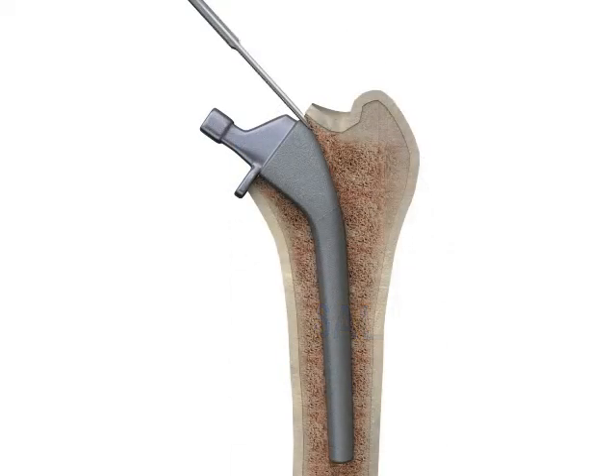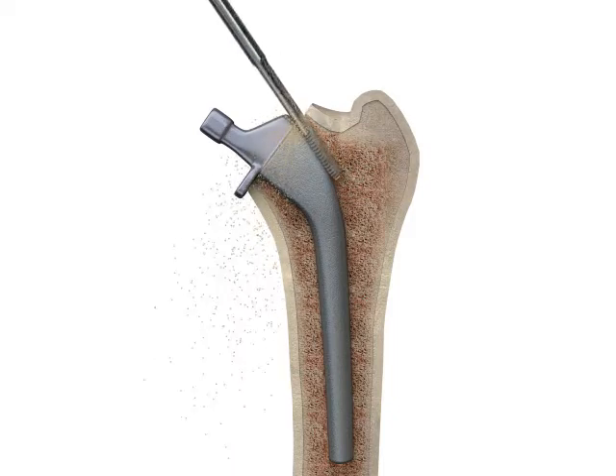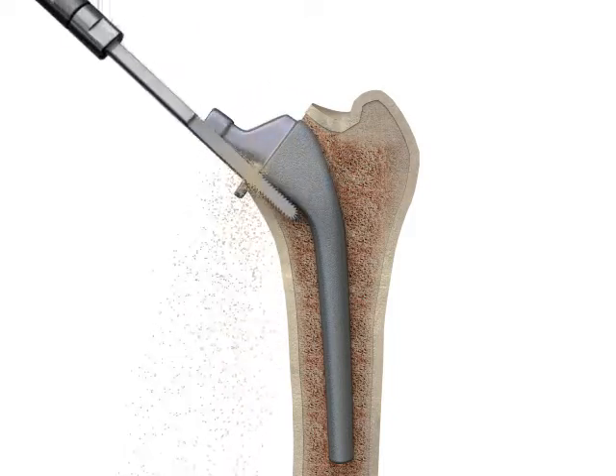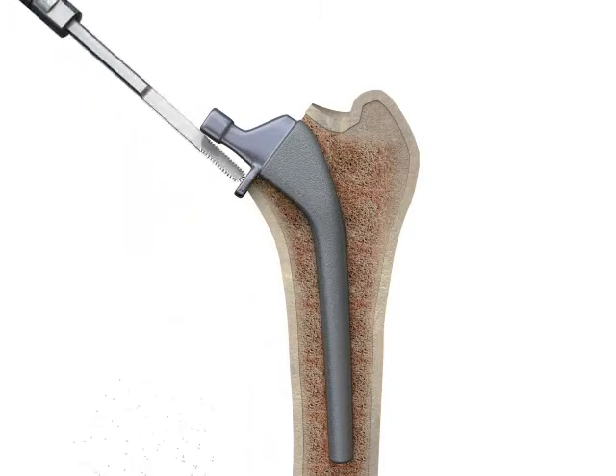A high-pitched noise will be heard when the active probe is in contact with the implant. Do not use heavy manual force while hearing the noise. It will rapidly fatigue the probe and give less than optimal performance. Once the slots are created, the 6 mm flat serrated probe can be used to break the interface of the remaining bony ingrowth.